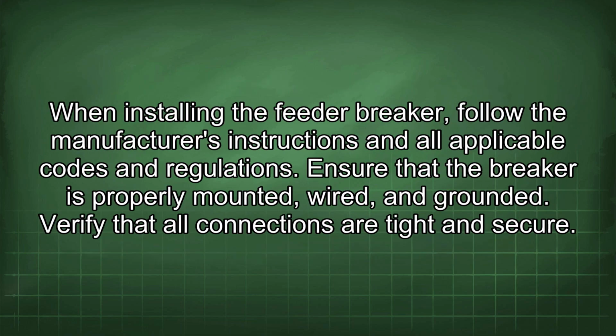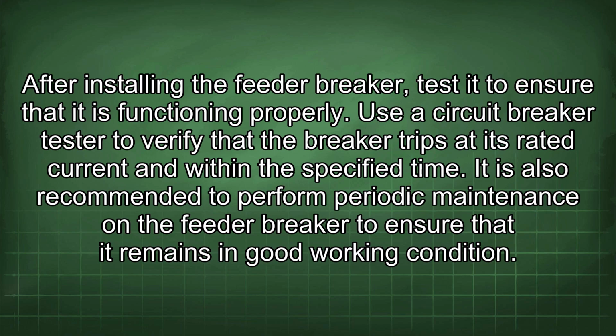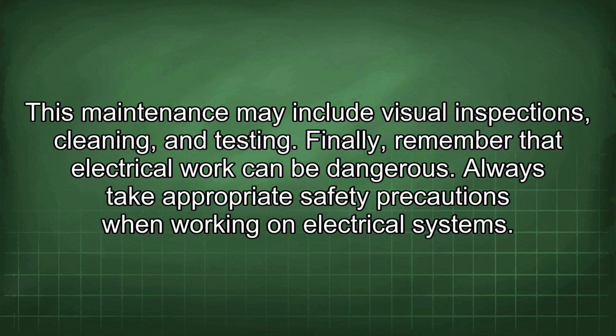When installing the feeder breaker, follow the manufacturer's instructions and all applicable codes and regulations. Ensure that the breaker is properly mounted, wired, and grounded. Verify that all connections are tight and secure. After installing the feeder breaker, test it to ensure that it is functioning properly. Use a circuit breaker tester to verify that the breaker trips at its rated current and within the specified time. It is also recommended to perform periodic maintenance on the feeder breaker to ensure that it remains in good working condition. This maintenance may include visual inspections, cleaning, and testing.